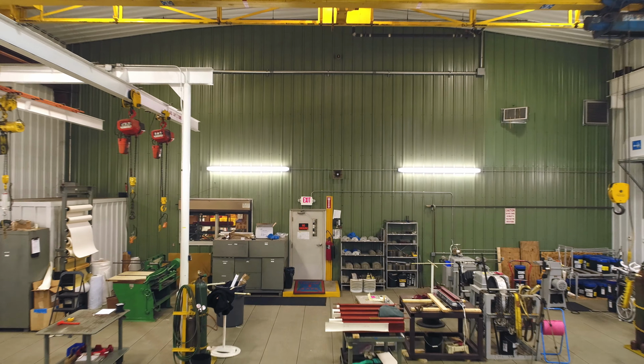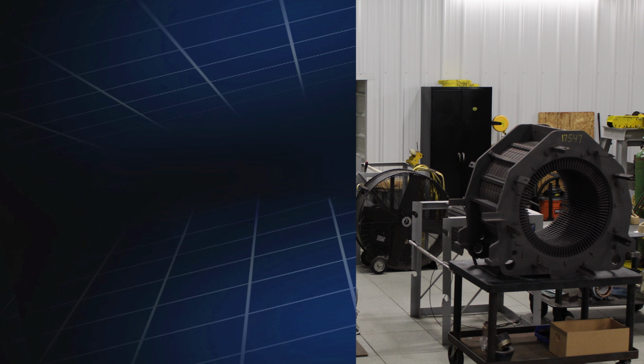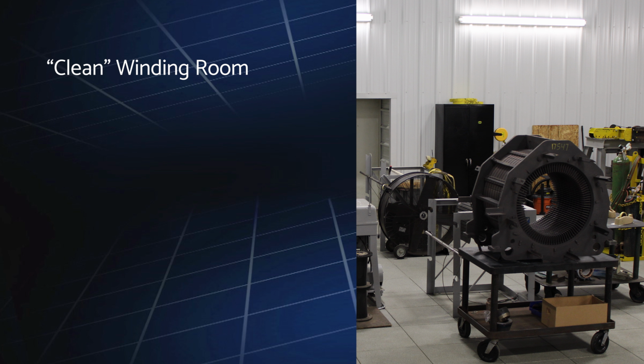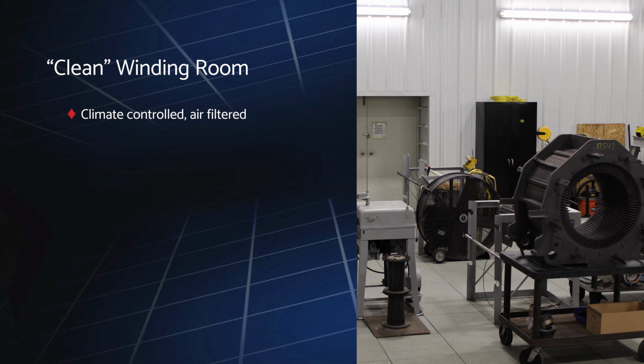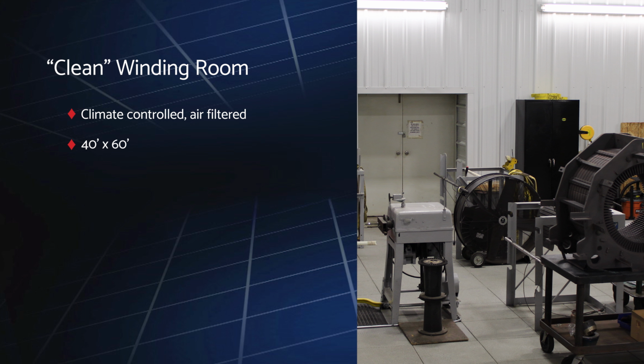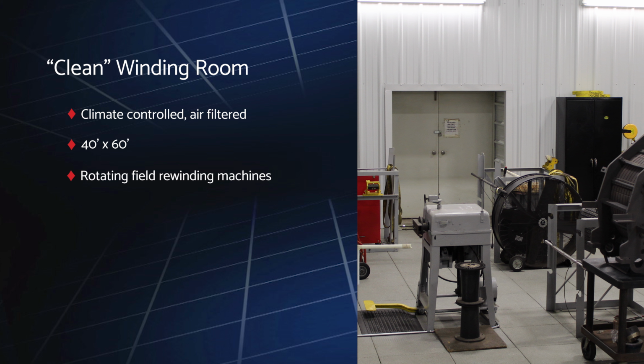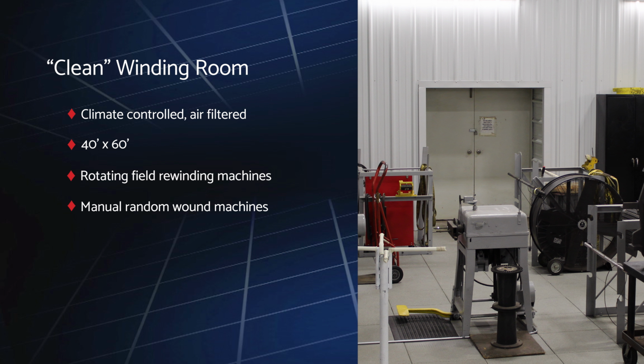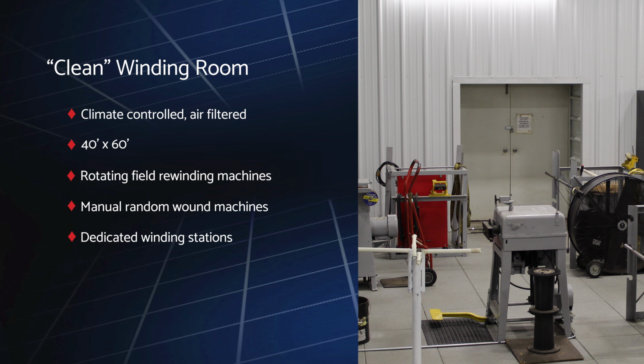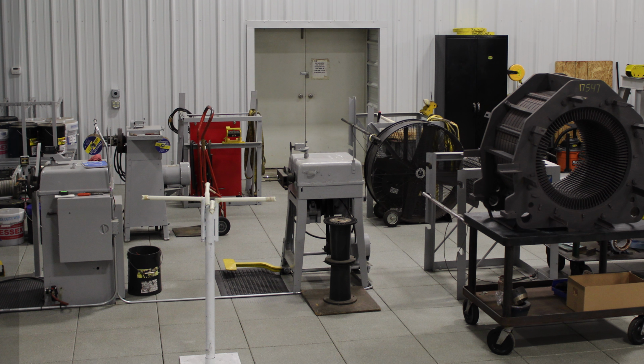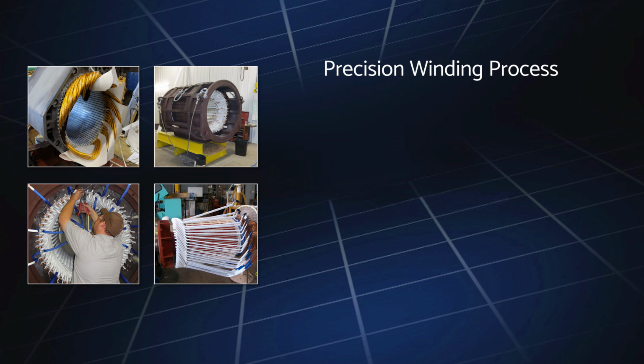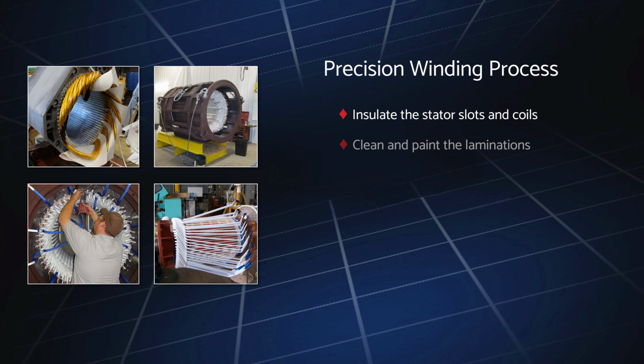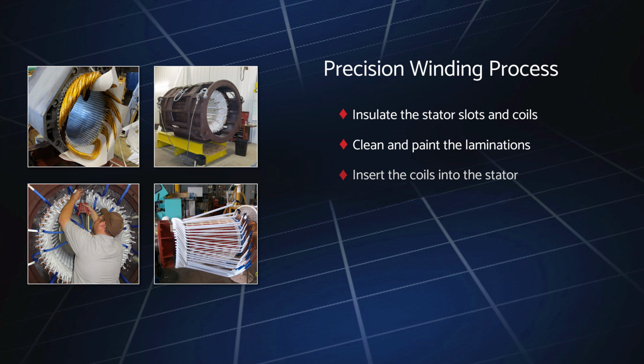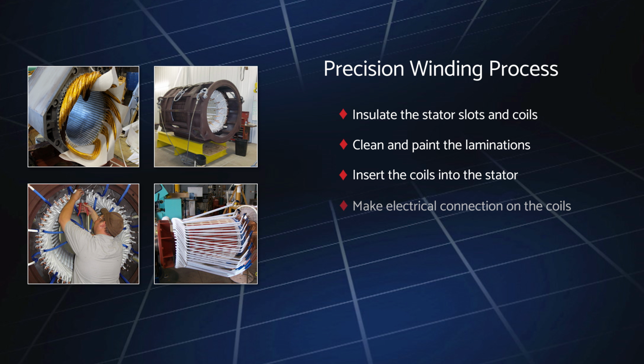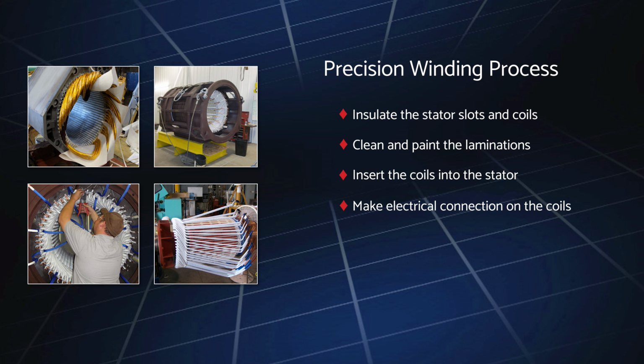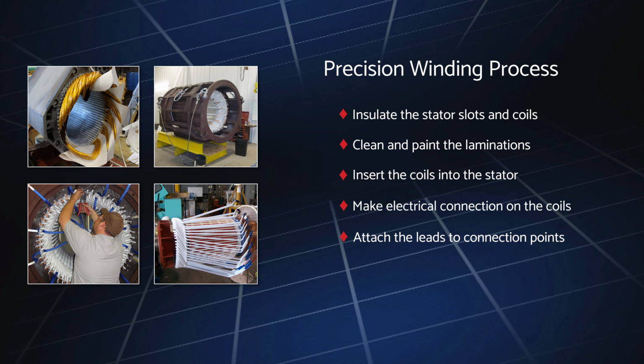The equipment is then ready for the rewind process and is delivered to our dedicated, clean, air-filtered, and climate-controlled winding room that is outfitted with top-of-the-line equipment, including rotating field rewinding machines, manual random wound machines, and dedicated winding stations, where we insulate the stator slots and coils, clean and paint the laminations, insert the coils into the stator, make the electrical connection on the coils, and attach the leads to connection points.